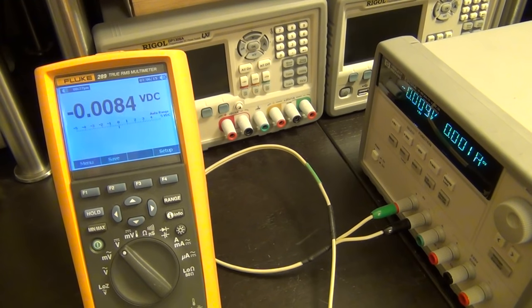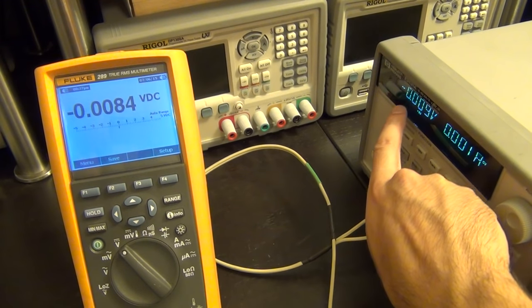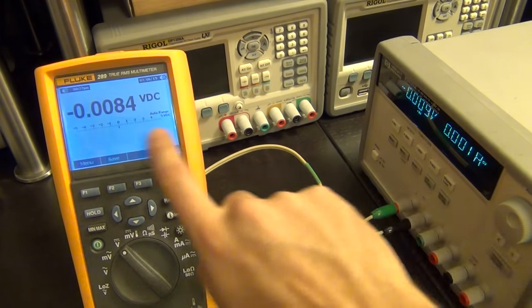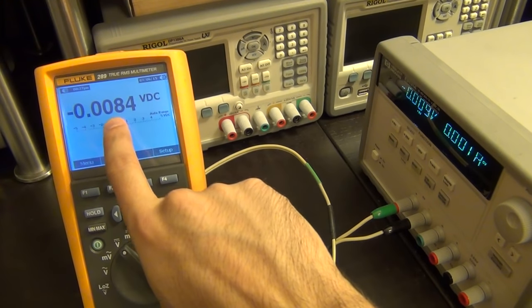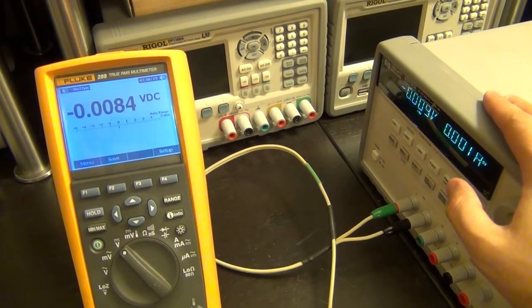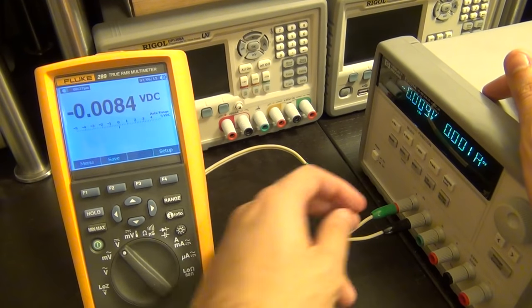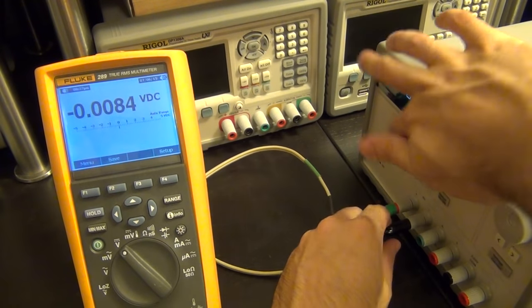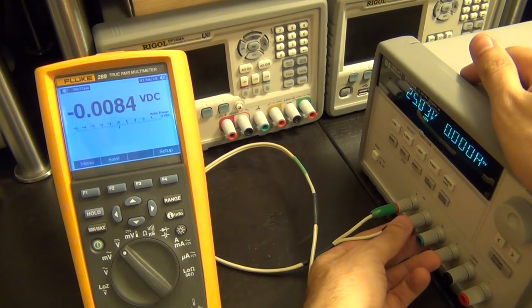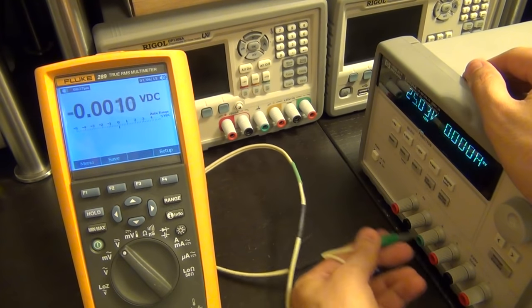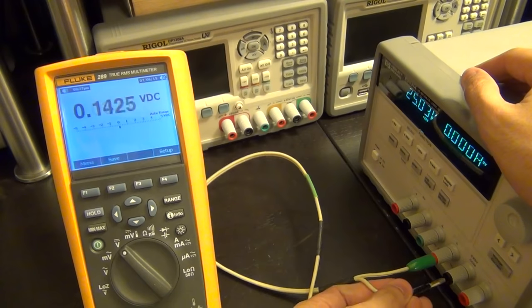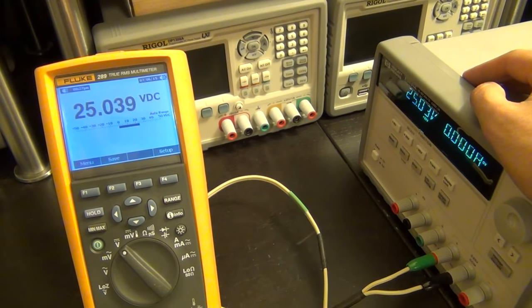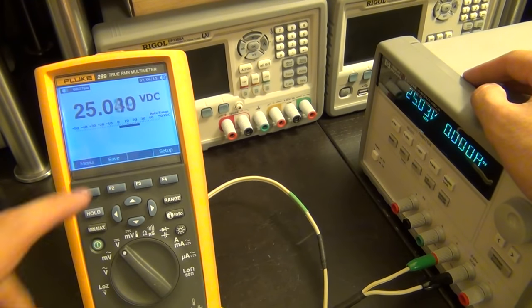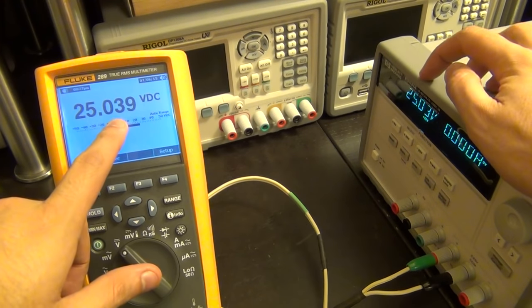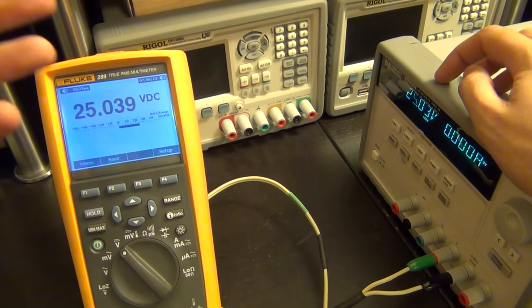And here we go. Let's do some measurements. And look at that. This thing says 0.009 negative, and this says minus 0.0084. So it's dead on, as accurate as you would ever want it to be. And now let's go to plus 25 volts. Right now it's set to 25.03. So we can go ahead and switch it over and see what it says. There we go, and check it out, 25.04 versus 25.03. So it is very, very close to what it's supposed to be.